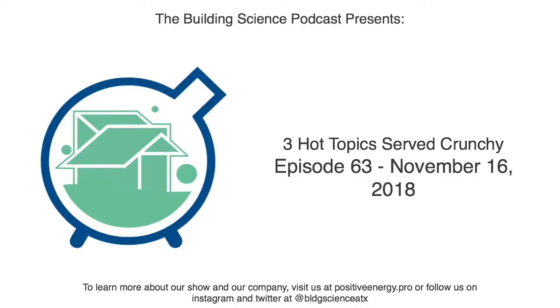And the CO2 can be an issue. Interestingly, we're in our conference room right now, the door is shut, and because of some noise issues with our ducts, the ducts are in the room with us, and so is the ERV. We have it off, and right now my CO2 is at like 1300, but when we turn that ERV back on, it'll go back down to 500-600. It doesn't get all the way down to 400, which is where it is in the morning. That's like outside air. You need a lot of air changes mechanically to keep it at 400.